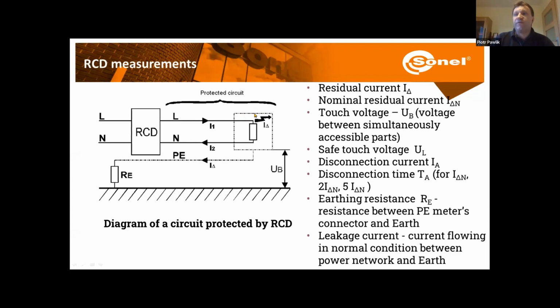But in case we have a fault situation, then the current flowing in and powering our device will divide. Some will return through the neutral channel, and some will return through the ground channel to the earth. Now the RCD will see that the current flowing in on the phase and flowing out on neutral, they are not equal. So then it's going to trigger and it's going to break and disconnect the power supply in our network.